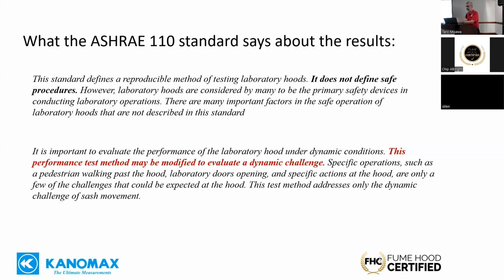So another thing that is said here is that ASHRAE 110, and this is right out of the standard, does not define safe procedures. So it doesn't really tell us that a hood's safe. And what do they say down in the second paragraph? This performance test may be modified to evaluate dynamic challenges. So what they're suggesting is that if you really want to know if a hood works, you need to test it under dynamic conditions. And we'll get into that in a moment.